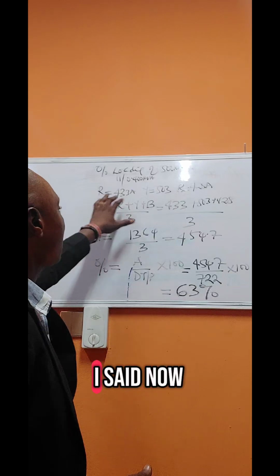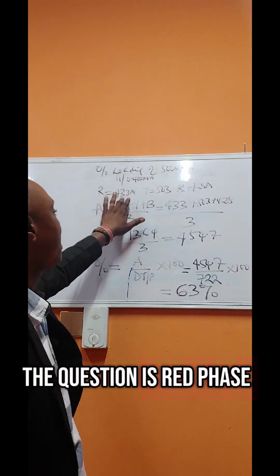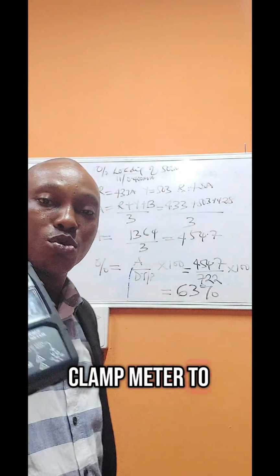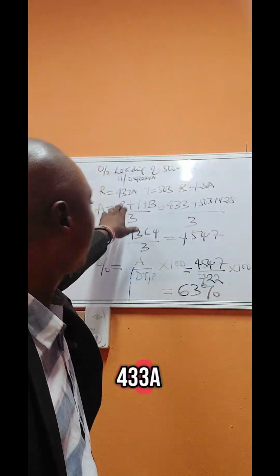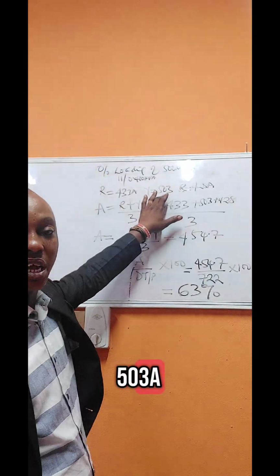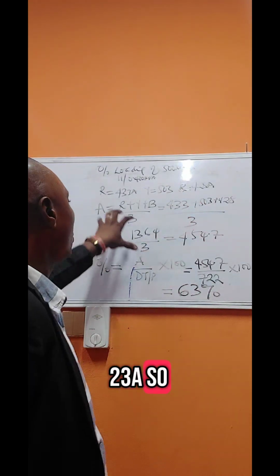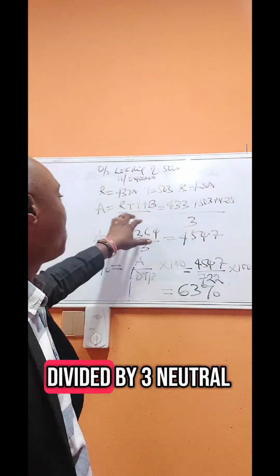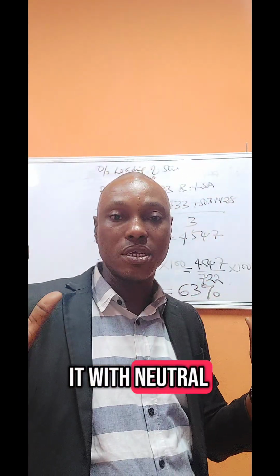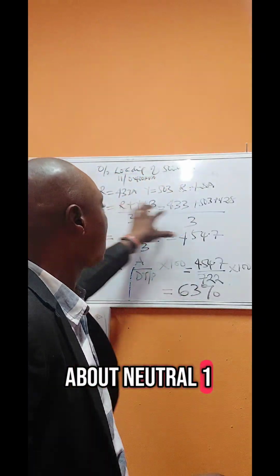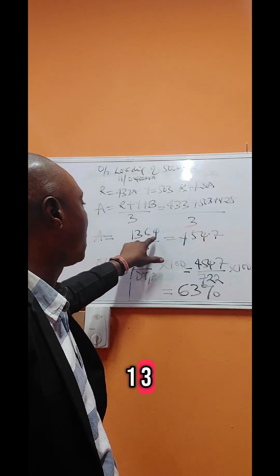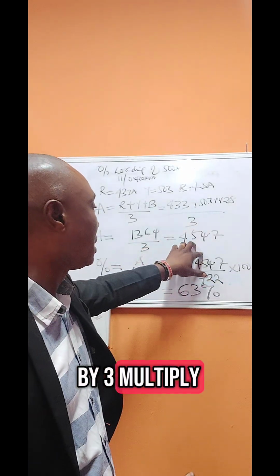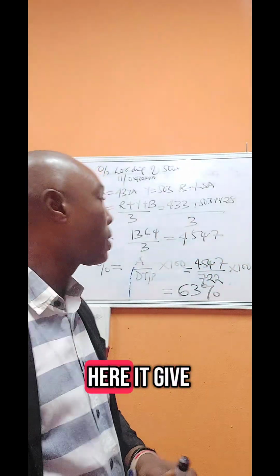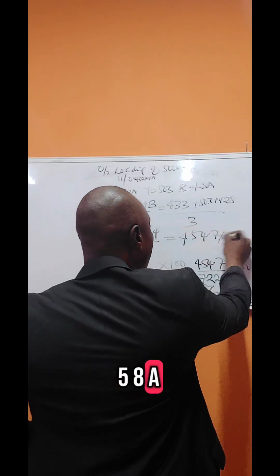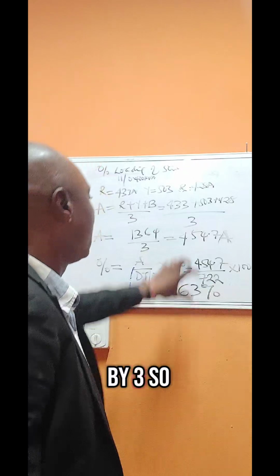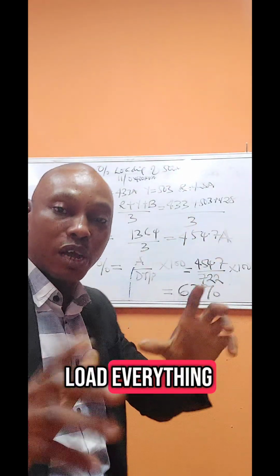Say for 500 kVA, the question is: when you use a clamp meter to check, the red phase is 433 amps, yellow phase 503 amps, blue phase 428 amps. You do your calculation: add the three together and divide by 3. Neutral, you don't worry about it. Neutral is negligible, you forget about the neutral. When you add the three phases together, it gives us 1364. You divide it by 3, and it gives us 454.7 amps. So this is the average load.